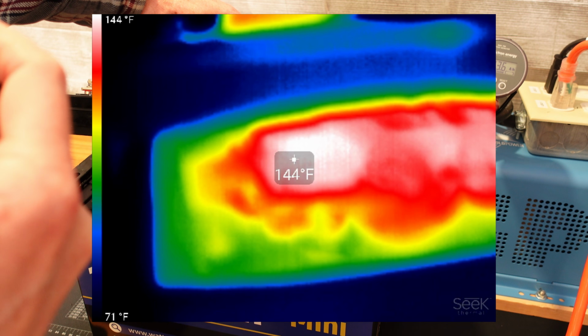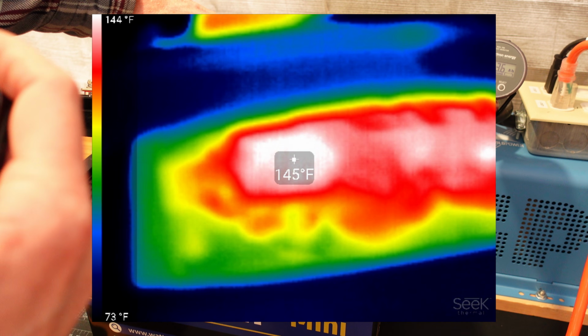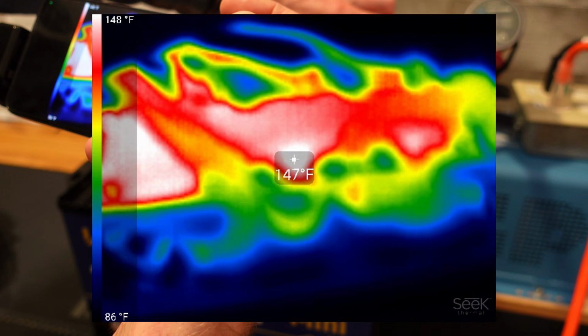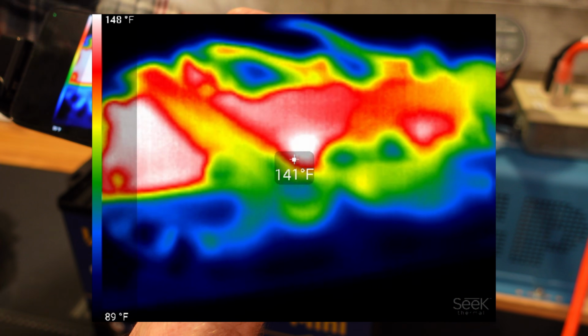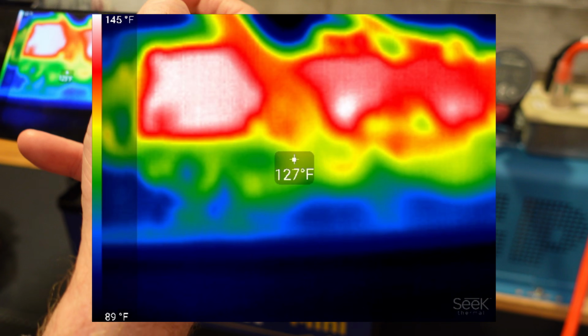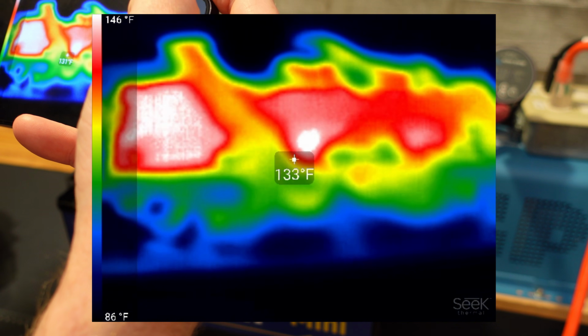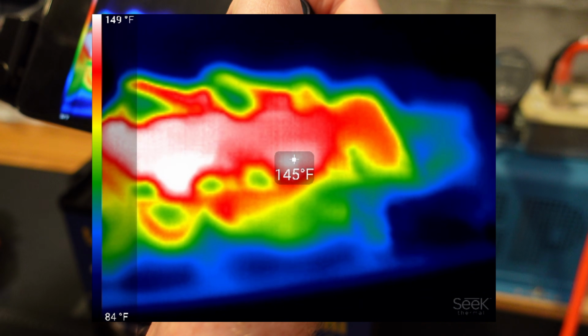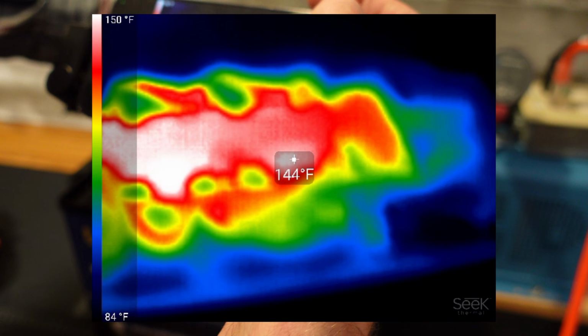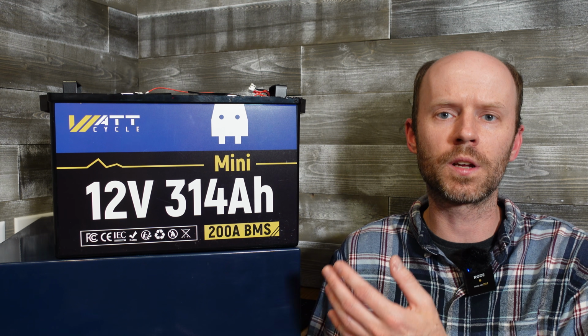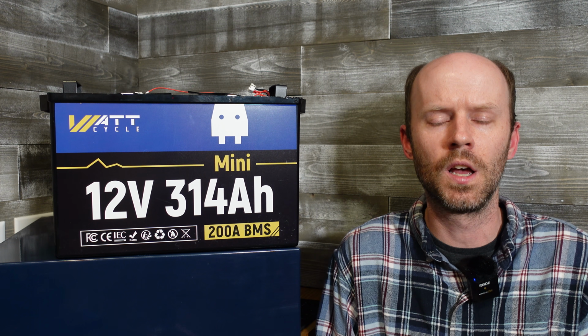So the top of the BMS is sitting at 144 degrees Fahrenheit. Oh, there's 147 there, what is that? 145 on the right, no issue with that test either. This battery is performing great, it handled the full current, averaging around 195 amps or so for the full duration of the test without issue.